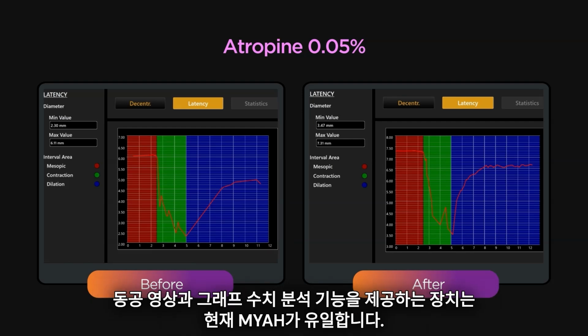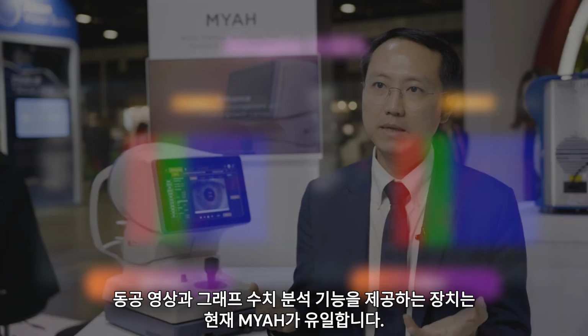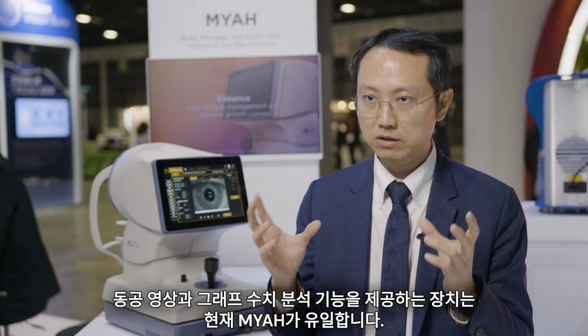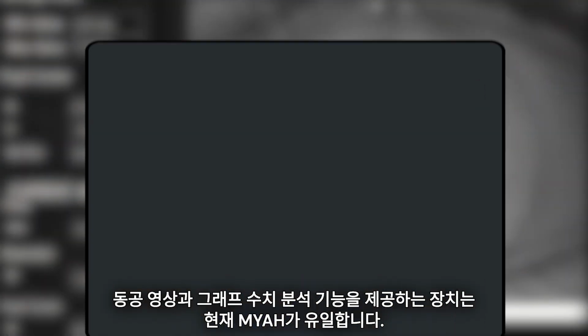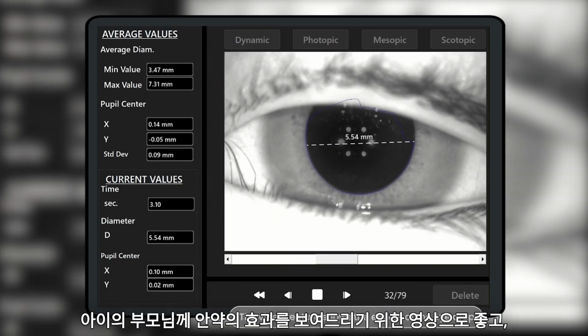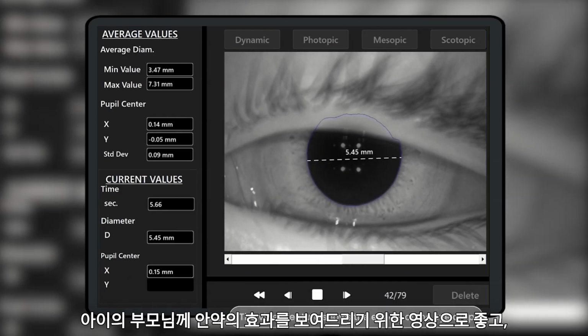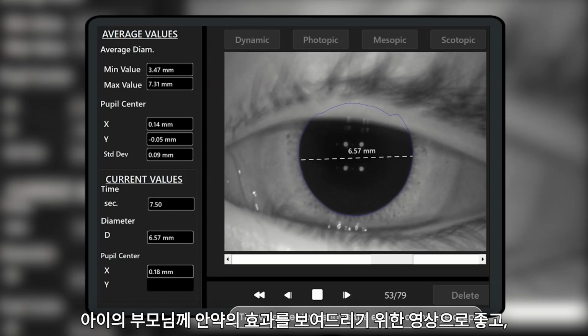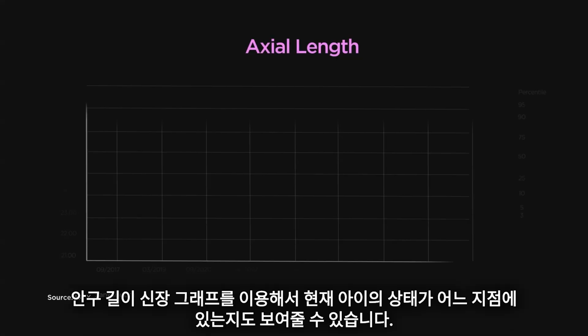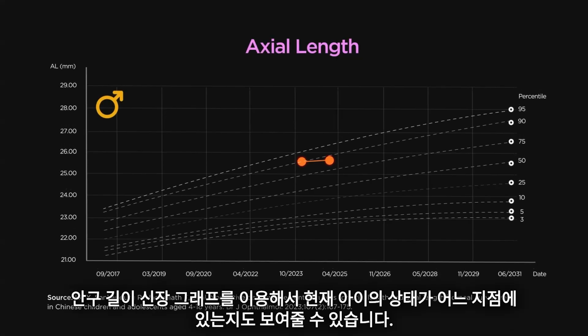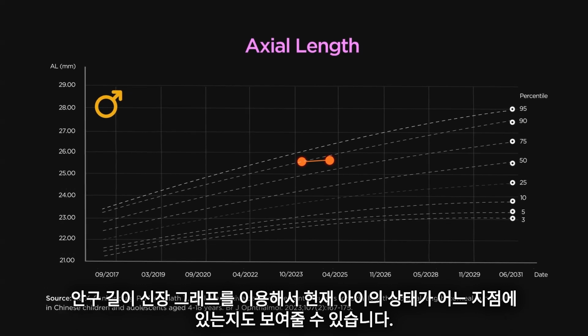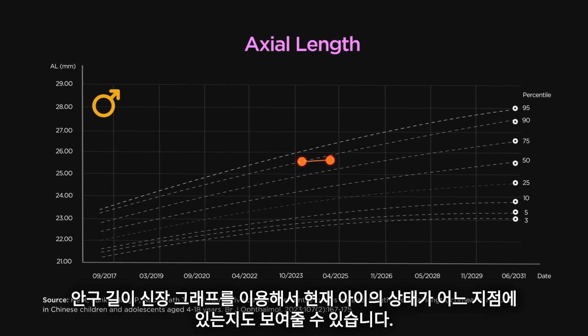This is the only device on the market at the moment that gives you this video recording capability as well as numerical analysis. This is beneficial in terms of having the video to show the parents the effect of the eye drop, and also having the growth chart to let the parents understand where the child is in terms of their axial length. So in terms of patient education, it helps me explain things faster.